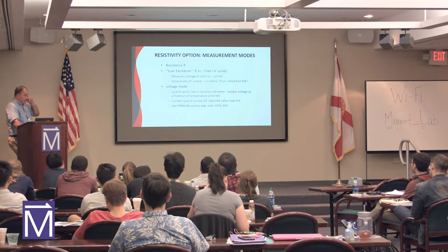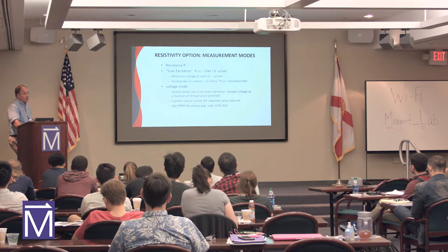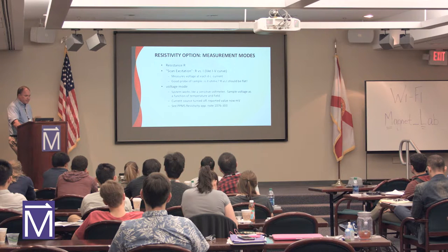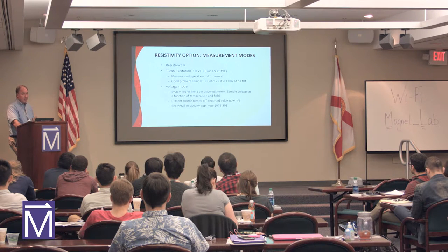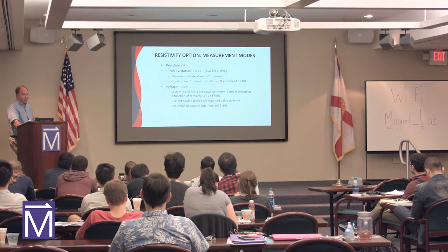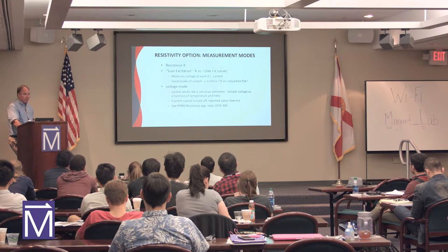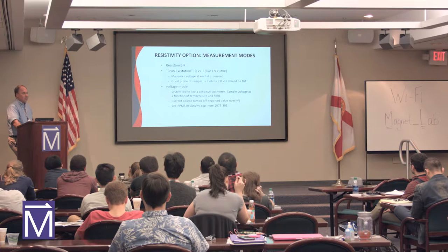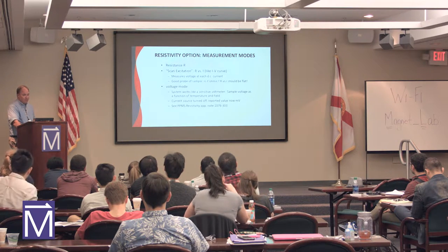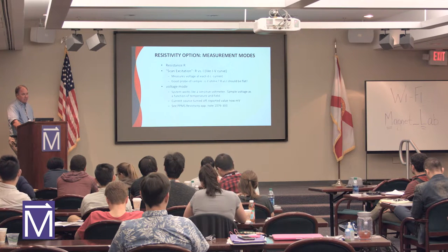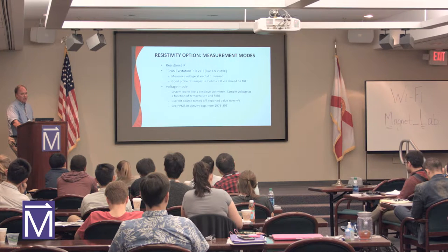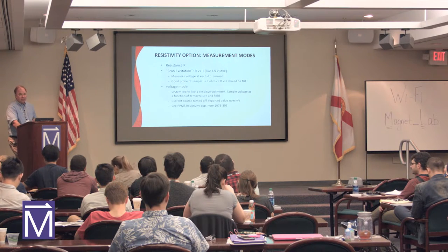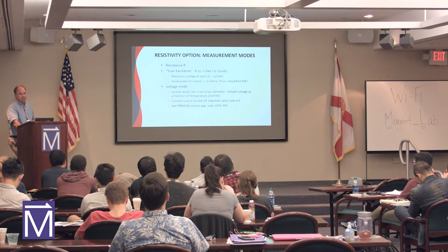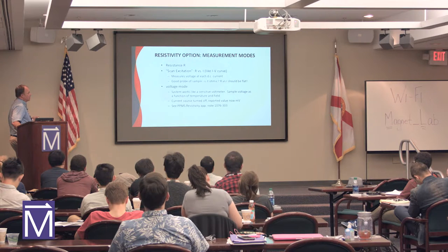We're doing the resistance measurement with the resistivity option. Scan excitation mode measures the voltage at each DC current, like an IV curve. And then you can also use the system in a voltage mode, so it's just a voltmeter. You can have a voltmeter across your sample to see if there's any induced voltages due to temperature or magnetic field changes. So it's another mode that you can run. The current's turned off in the system, and it's reporting the voltage that's generated across the sample. There's an application note that talks about how you can use the system as just a sensitive voltmeter. So that's built into all those systems.